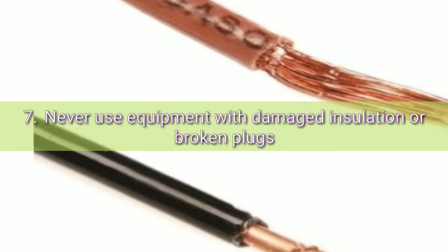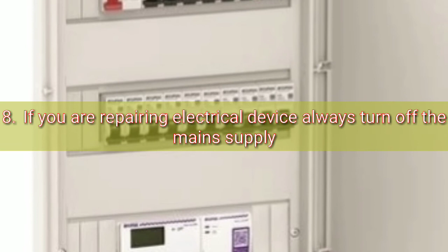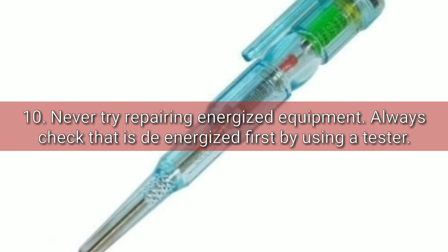Seventh point is never use equipment with damaged insulation or broken plugs. Next point is if you are repairing an electrical device, always turn off the mains supply. Next point is always use insulated tools while working. Never try repairing energized equipment. Always check that it is de-energized first by using a tester.